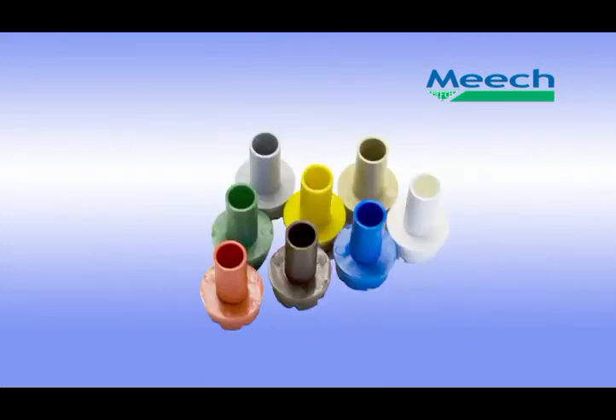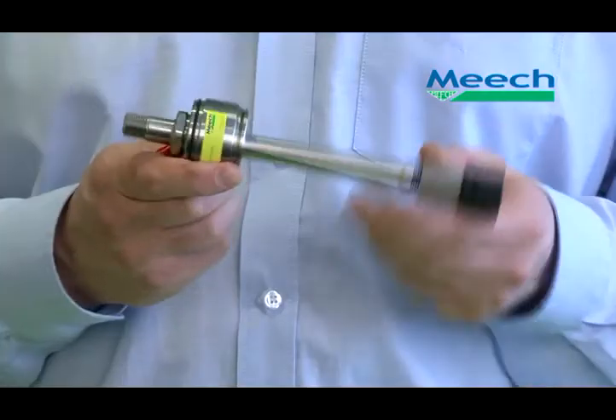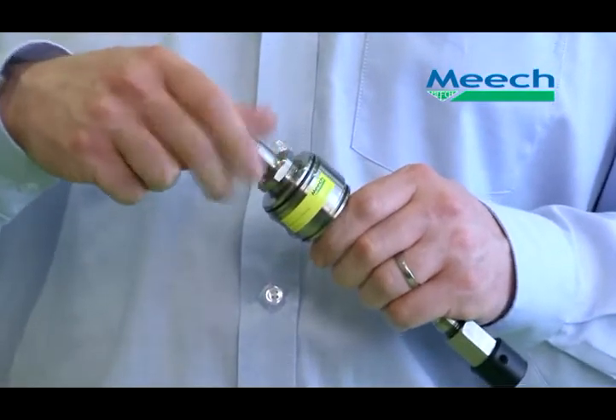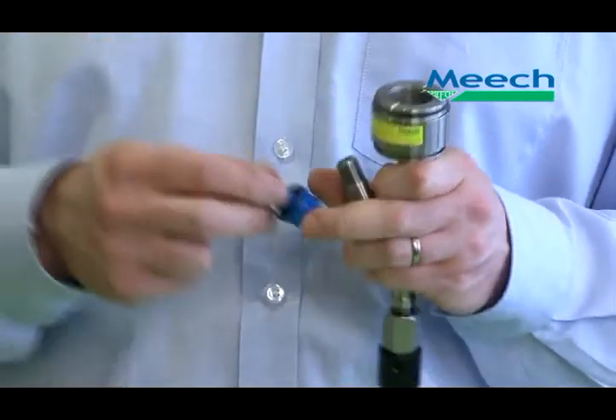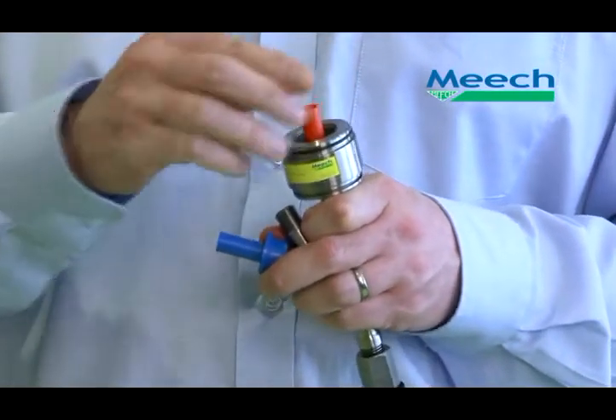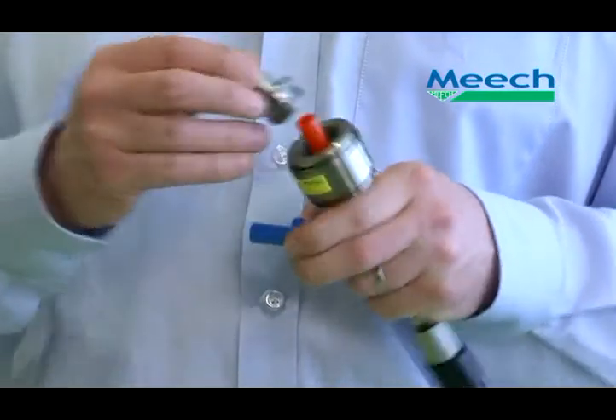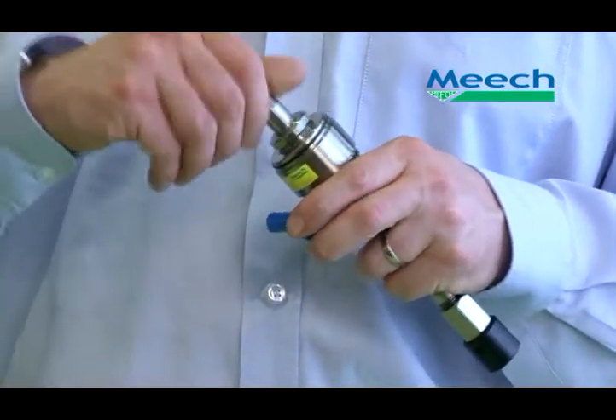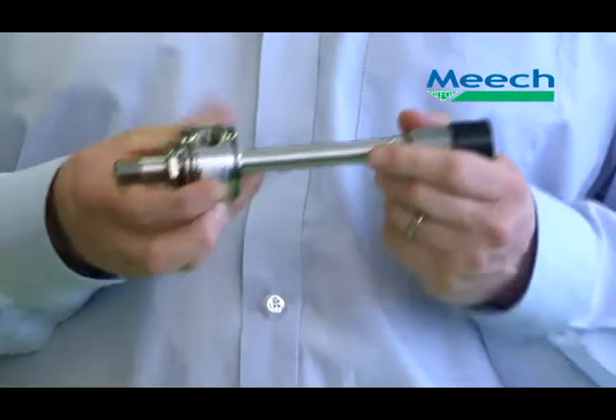The second way to control the air temperature and flow is through the generator used within the Vortex. The generators control the air consumption and influence the achievable temperatures. 8 generators are available for the medium Vortex tubes, 4 with a high cold fraction and 4 with a low cold fraction. Each generator will achieve a different airflow and temperature range. The 8 generators offer 4 different air consumptions: 10, 15, 25 and 35 CFM. Generators can be changed according to the application needs. As shown, this can be done quickly and relatively easily.